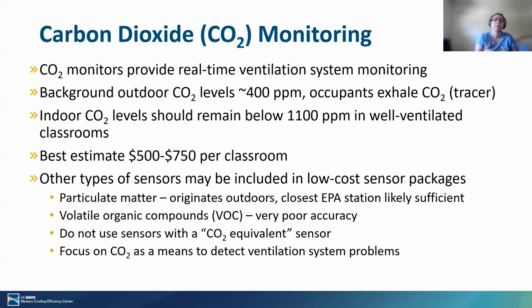So carbon dioxide monitors provide real-time ventilation system monitoring. Basically the way this works is outside, our CO2 levels are around 400 parts per million. Well, they're climbing, maybe they're 425. And then inside, occupants are exhaling CO2, and so that's essentially a tracer gas. So if our room is within its maximum occupant density, so if that room was designed for, and the ventilation system was set for, 30 people, and we have no more than 30 people in that room, and everything is working correctly, those indoor carbon dioxide levels should stay below 1100 parts per million.